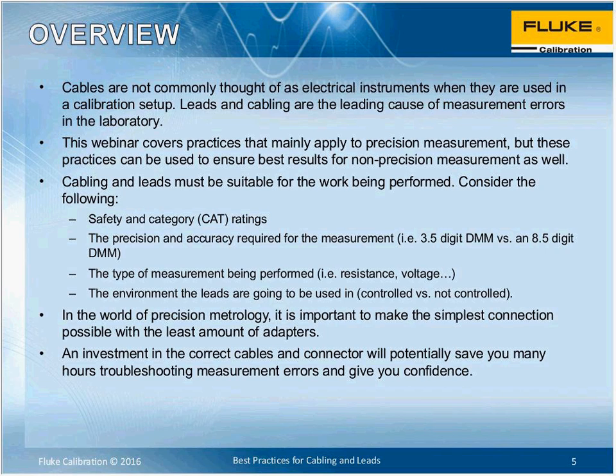It covers mainly precision measurement, but these practices can be used for what I'll call non-precision measurement as well. When talking about precision measurement, typically we're talking 6.5 digit or higher DMMs. We're talking about transfer measurements, calibrating the calibrator. But I just mentioned we will be talking about some lower end DMMs as well, and some of the functions that go along with that.